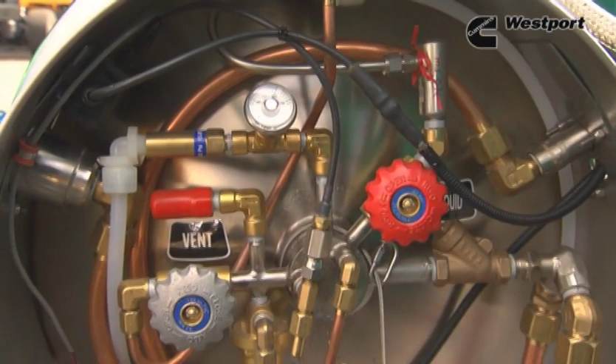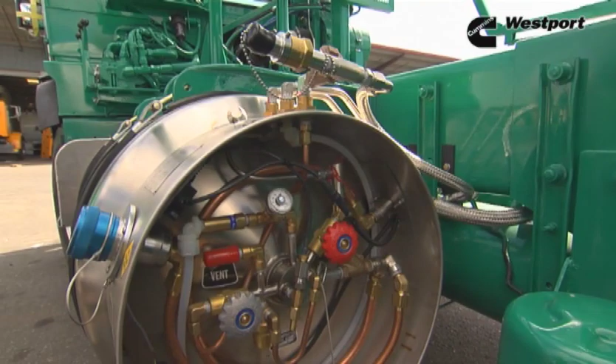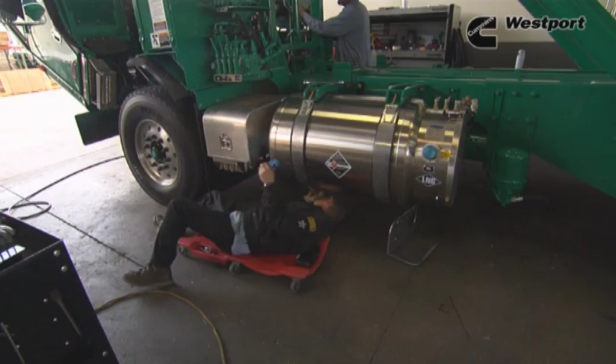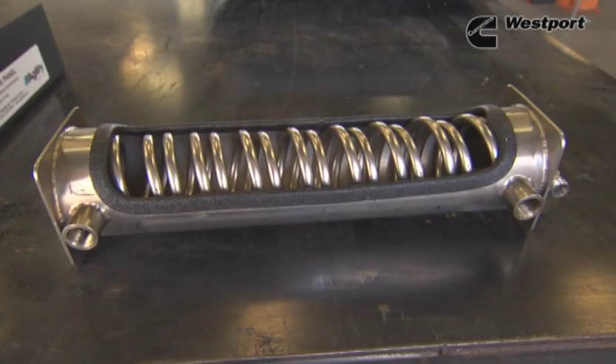A typical LNG tank will have a capacity of 60 or 75 DGE, and usually there will be one or two of these tanks mounted on the vehicle. LNG requires about half the storage space as CNG for an equivalent amount of energy. Unique to the LNG system is that it incorporates a vaporizer to warm the LNG to a gaseous state for delivery to the engine. When the engine is not running, the LNG fuel in the tank will slowly return to the gaseous form as the fuel warms, increasing the fuel pressure in the tank.